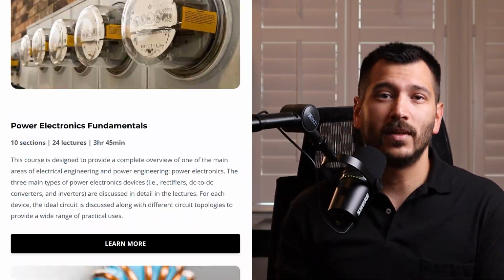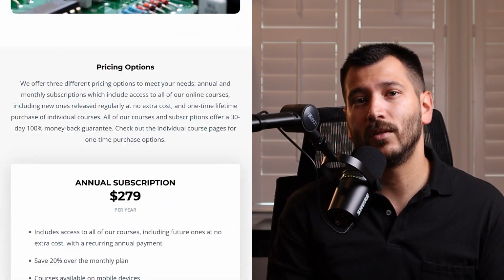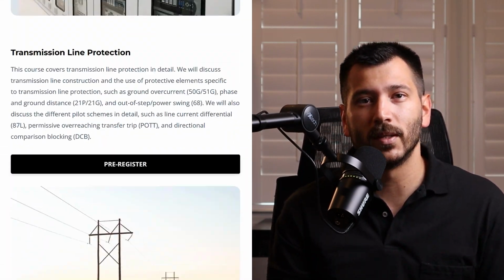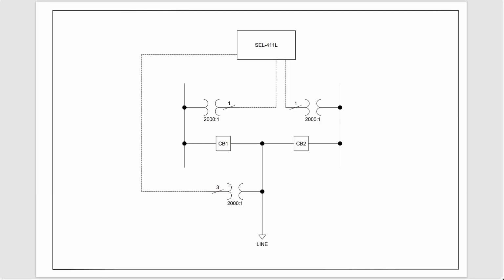All right, so let's jump right into it. Let's see how we can set up the Synchronism Check element using the SEL-411L protective relay. So let's say, for example, that we have a 230 kV substation that looks like this, where we have a double bus, double breaker arrangement. And for this example, we'll assume that the line voltage is connected to the Y terminal of the relay.